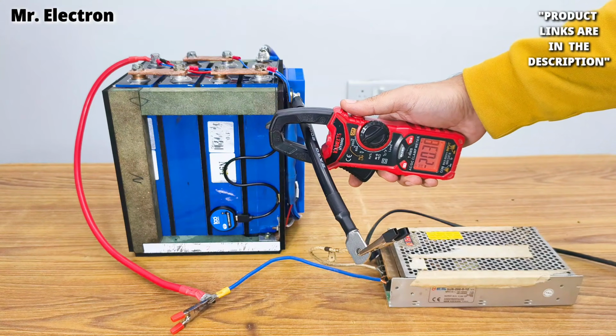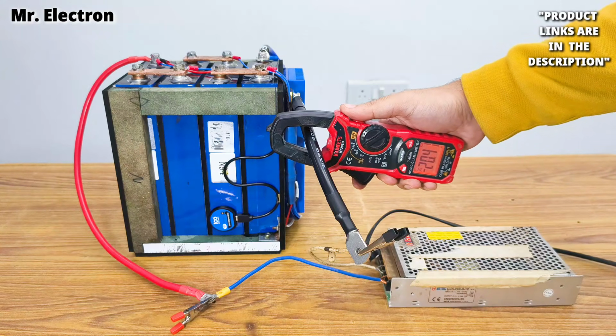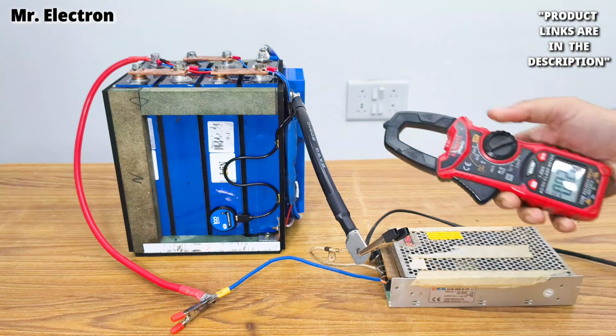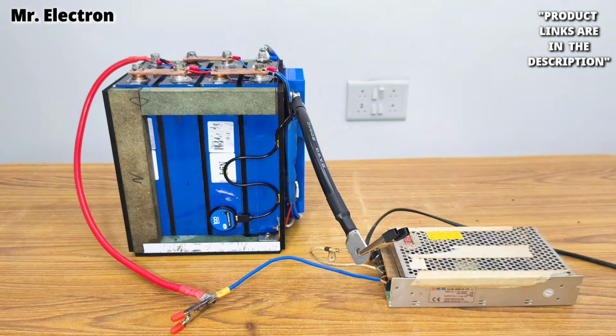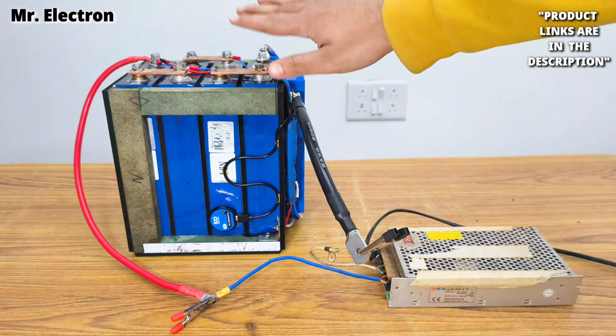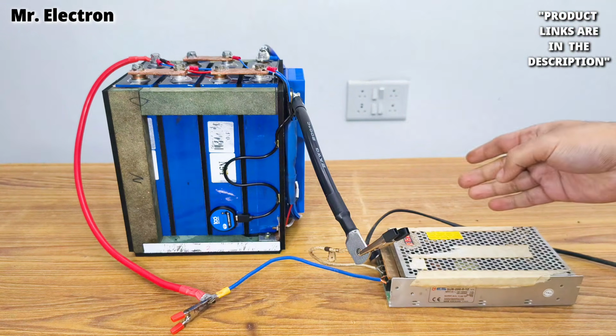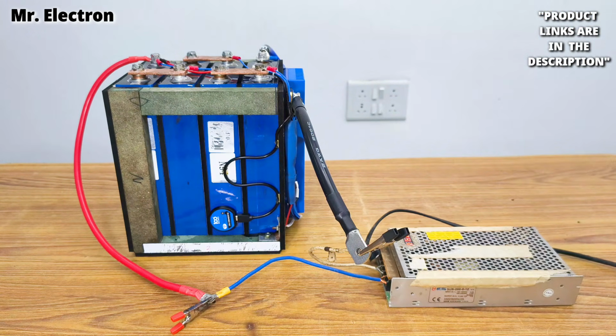The safest and long life charging current for a 100 ampere rated battery pack is 20 amps, and 30 amps is also fine. But as you go higher, it's not very good for the battery pack, reducing the number of cycles. So it's better to stick around 30 or 35 amps, the sweet spot for fast charging as well as long life and higher cycle count.